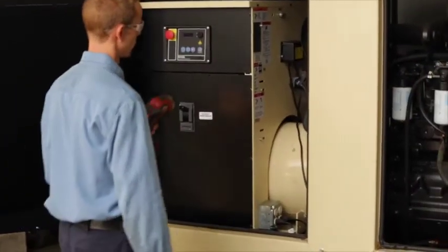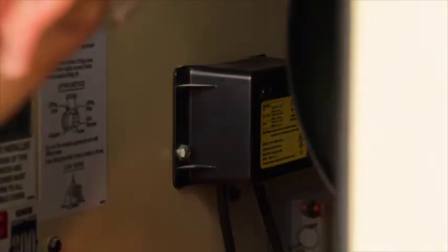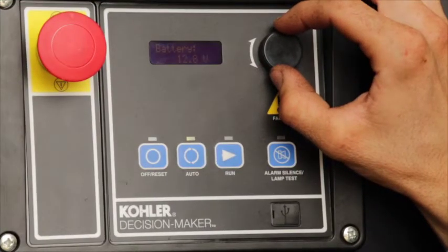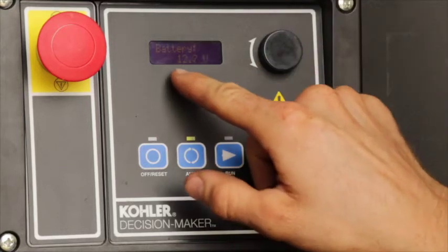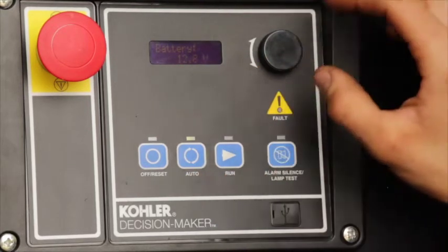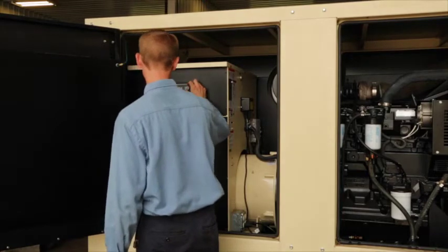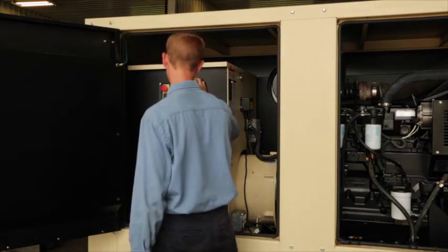For the fault warning battery charger failure, check the charger status lights using the legend on the charger and verify the charger is correctly plugged in. If the unit does not crank or it clicks, use the control panel's scrolling display to check the battery voltage during a start attempt. If the unit still fails to start, then call your service provider.